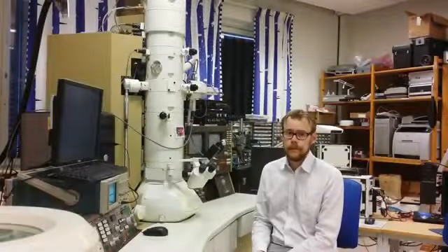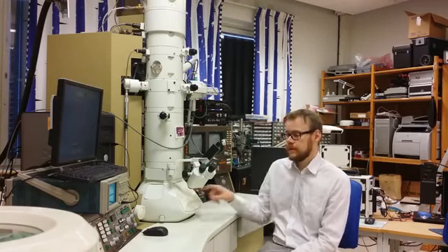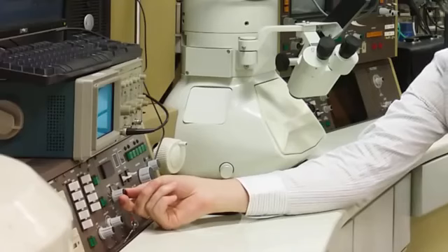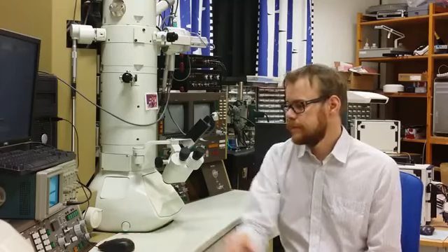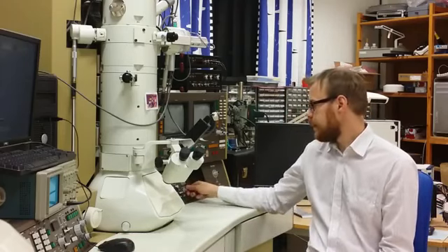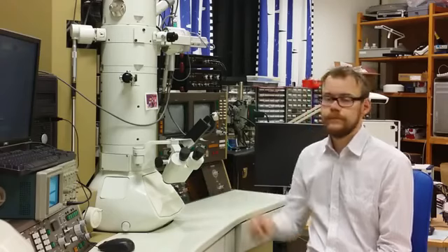Now I have turned on the lamp again and put back this protective cover screen. So how to shut down the microscope: you basically do the reverse procedure of starting it. So first you turn off the filament. After that you go down to 150 kilovolts in accelerating voltage. Then you turn off the high voltage. Turn off the computer screen. And that's it.